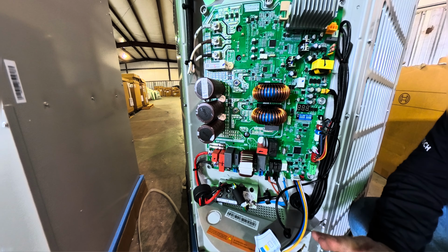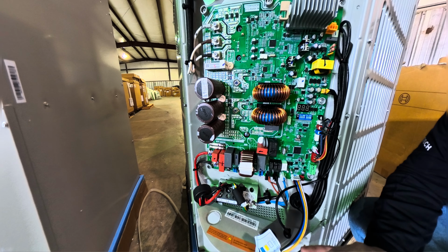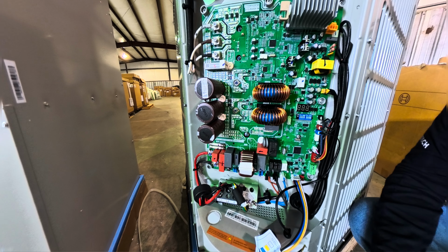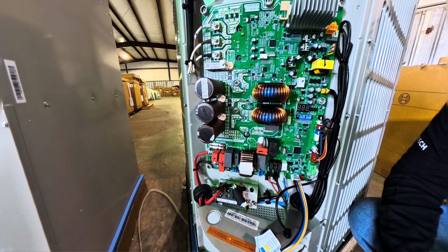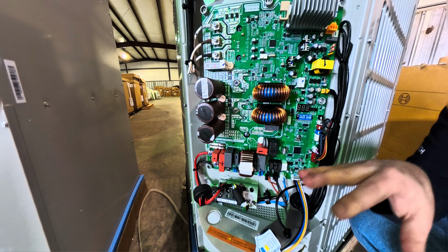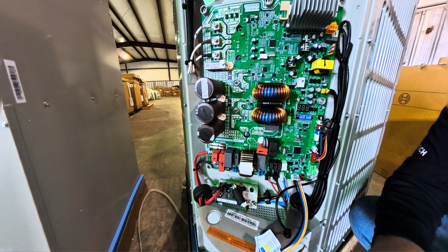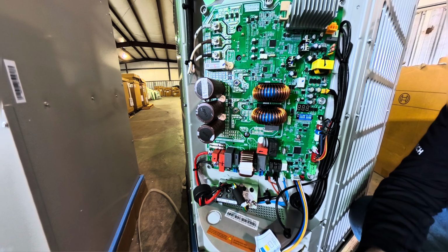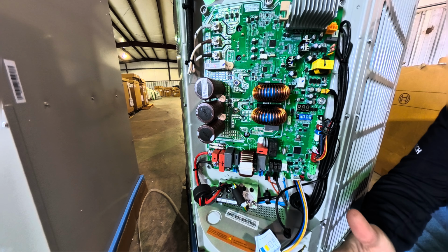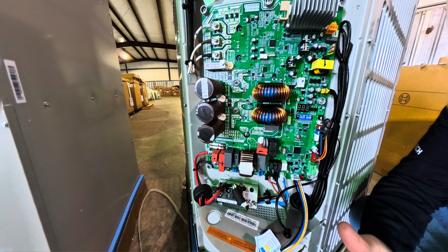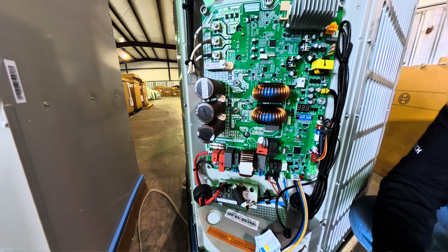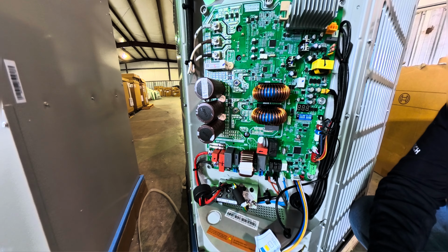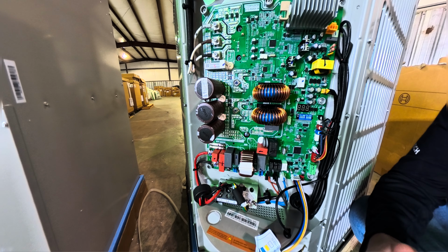Right now we're looking at a 5-ton outdoor unit control board, okay? We could put this on a 2-ton air handler and it is gonna ramp down. This thing's capacity, it can ramp down to around 15,000 BTUs, and it can actually ramp up over 5 tons of capacity to 66,000 BTUs. So that is phenomenal. That's super cool for those really cold days when you need extra BTUs, or on them really hot days when you need extra BTUs. This thing can ramp above capacity.